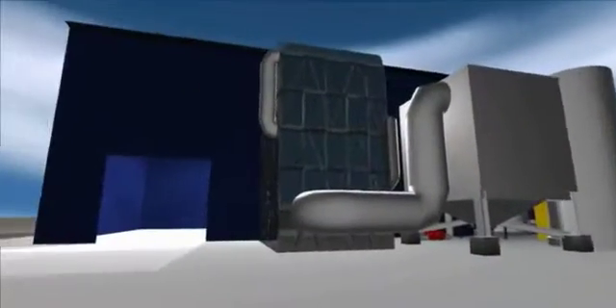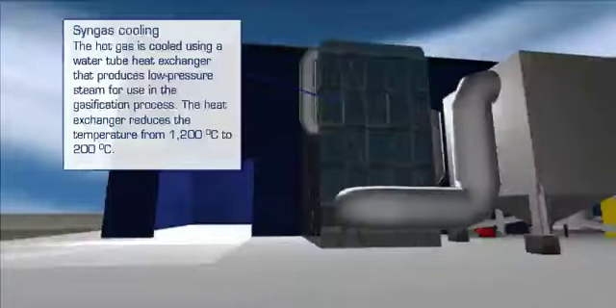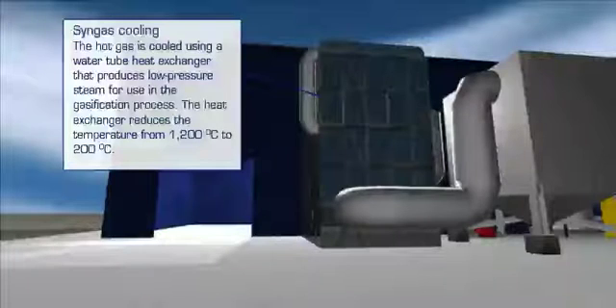Let's take a look outside. The hot syngas exits from the plasma converter at approximately 1200 degrees Celsius and is then cooled in a water tube heat exchanger to reduce the gas temperature to 200 degrees Celsius. During this process, energy is recovered in the form of low pressure steam, and a proportion of that steam is used in the gasification process.